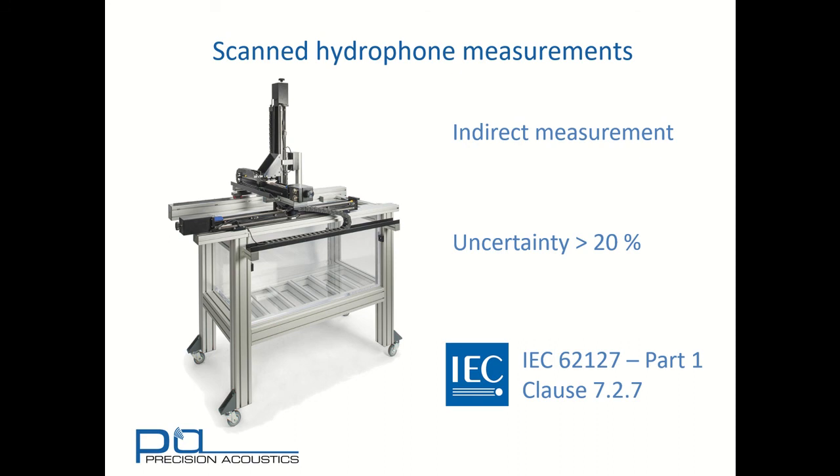For further details, one can consult IEC 62127 Part 1, specifically Clause 7.2.7, for further information on power determination by scanned hydrophone measurement.